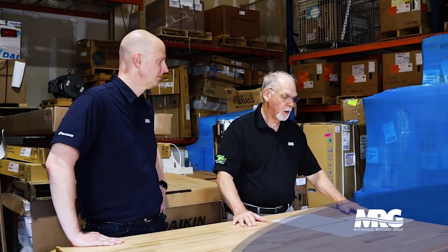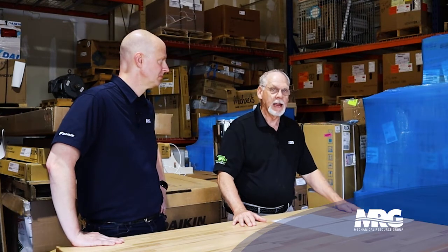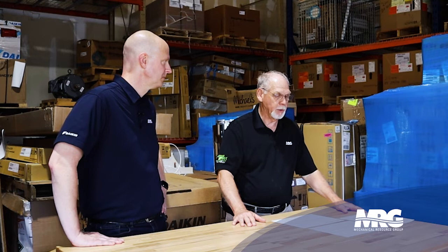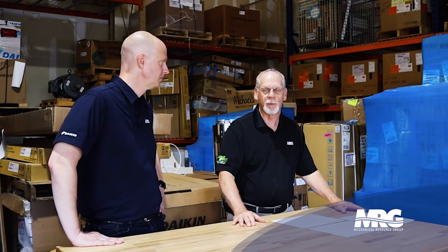The other thing that has happened over the years, everybody was trying to come up with a more economical way of installing things, and they were looking at different materials. We had the B-vent, which is a relatively inexpensive material. The condensing boilers took a stainless steel material to take care of the acidic conditions, and it got more expensive. They looked for some other materials, and they could use some PVC if they used direct air inlets. If they were bringing air in, not from the room, but from outside, they could use PVC.